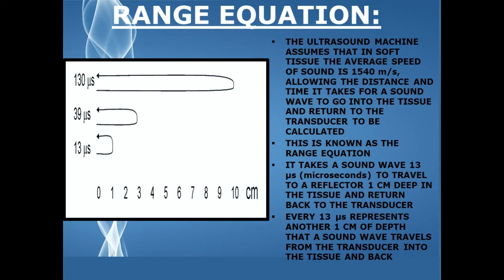The ultrasound machine assumes that in soft tissue, the average speed of sound, which is the propagation speed, is 1540 meters per second, allowing the distance and time it takes for a sound wave to go into the tissue and return to the transducer to be calculated. This is known as the range equation. It takes a sound wave 13 microseconds to travel to a reflector one centimeter deep in the tissue and return back to the transducer.